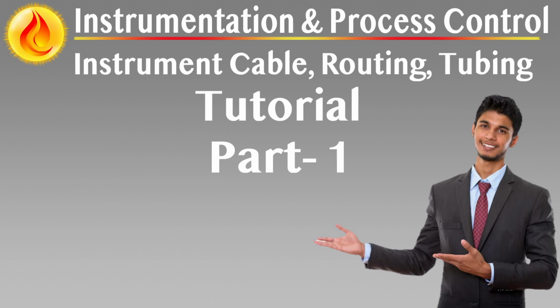Solid conductors. Recommended for field cables due to mechanical stability and termination clarity. Minimum diameters 1.32 millimeters for single core, 0.8 millimeters for multi-core. Stranded conductors. Permissible for internal cabinet wiring only. Require crimped wire pins/lugs for screw-type terminals to ensure gas-tight, corrosion-free contact. Solid conductors must not be used with crimp-on pins.